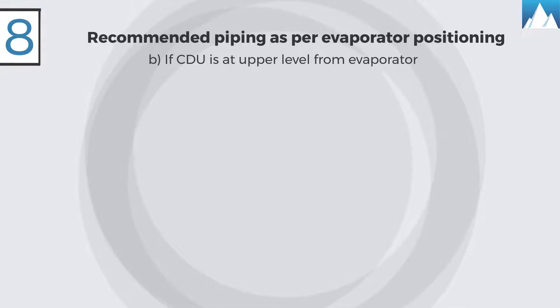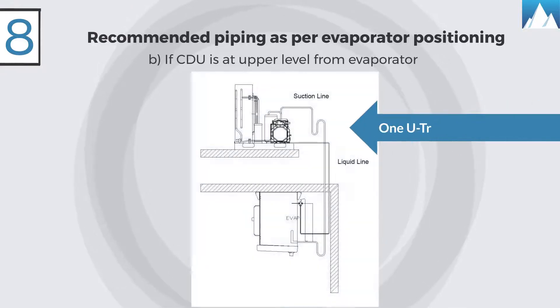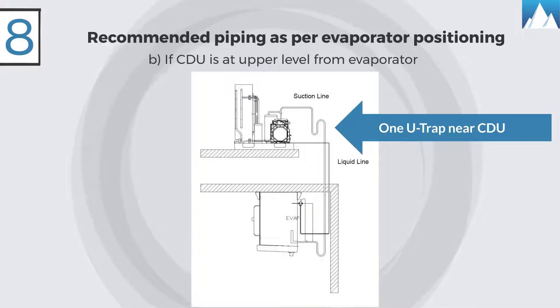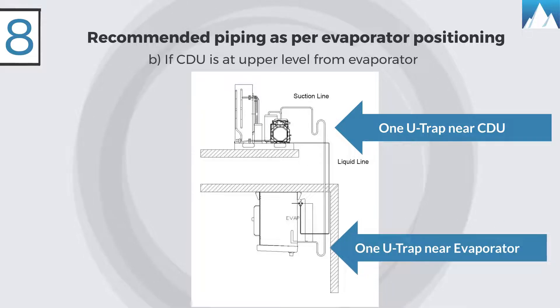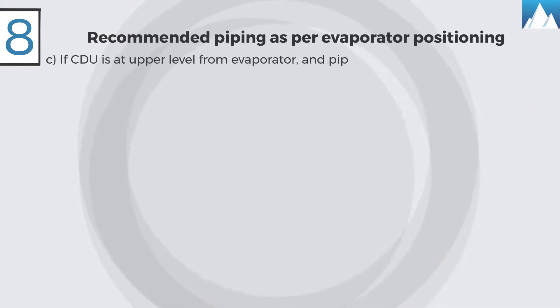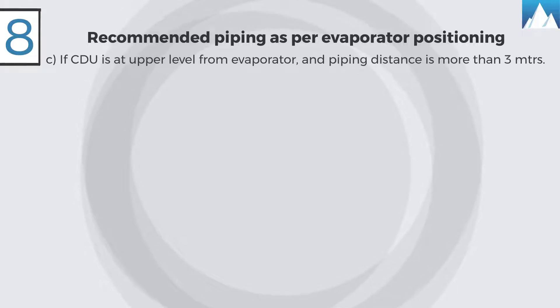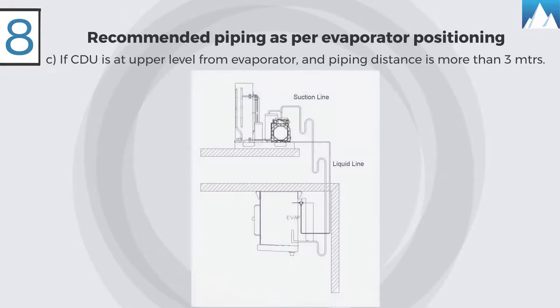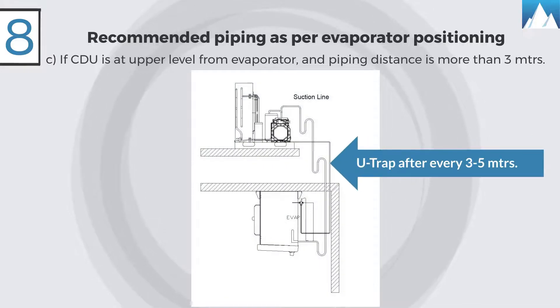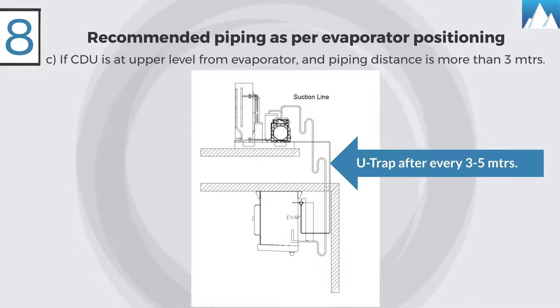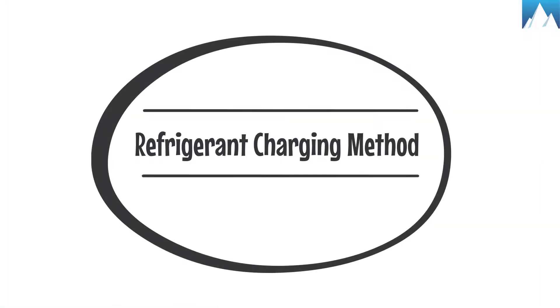B, if the condensing unit is at upper level from the evaporator, give U-traps — one near the suction line of the condensing unit and one near the evaporator. C, if the condensing unit is at upper level from the evaporator and piping distance is more than three meters, give U-traps at a distance of every three to five meters in the suction line of interconnected pipes.